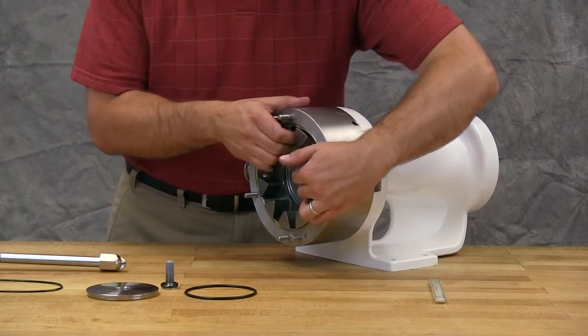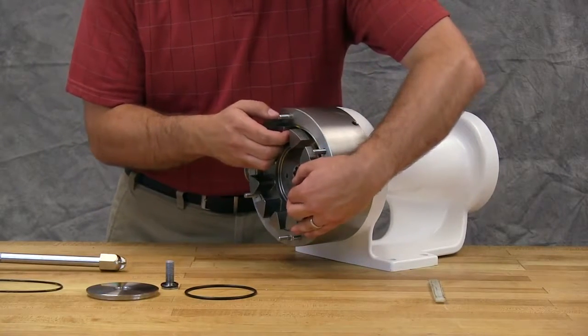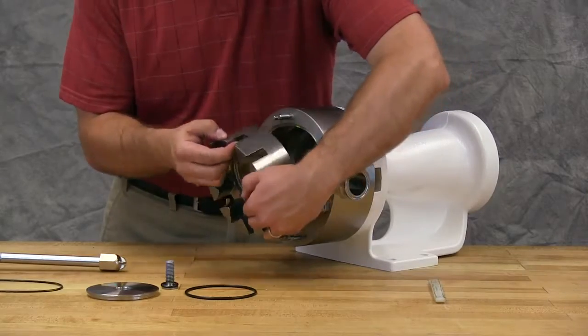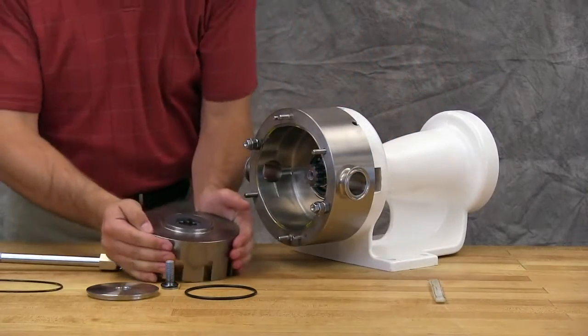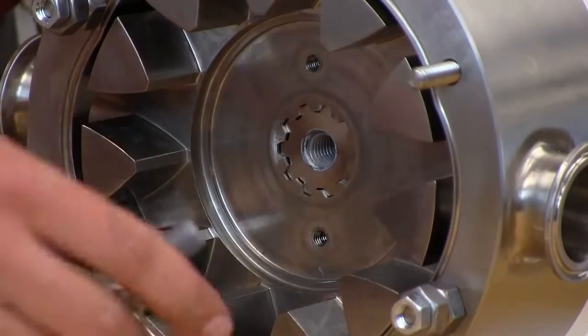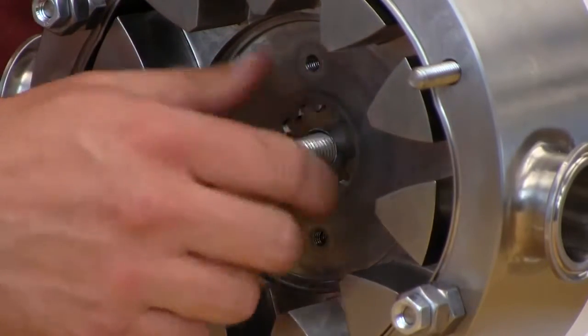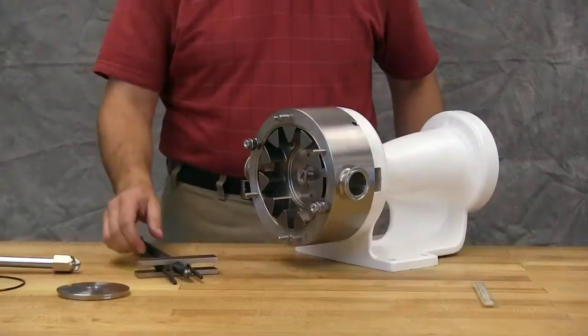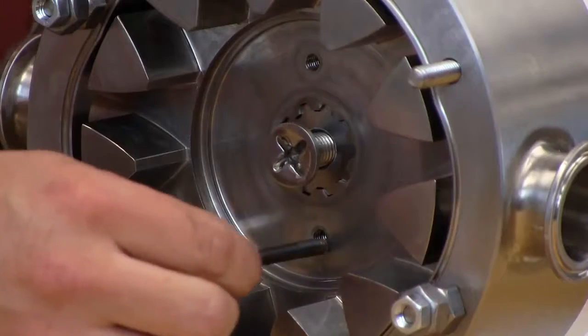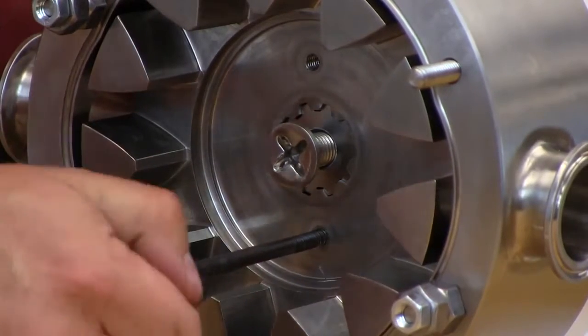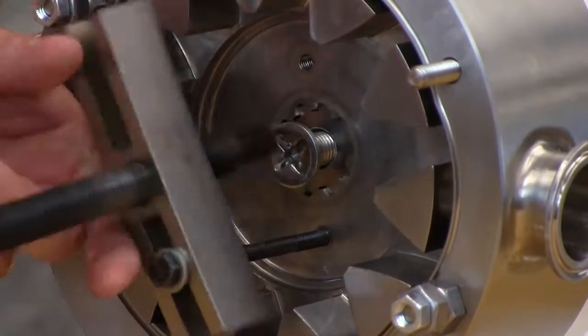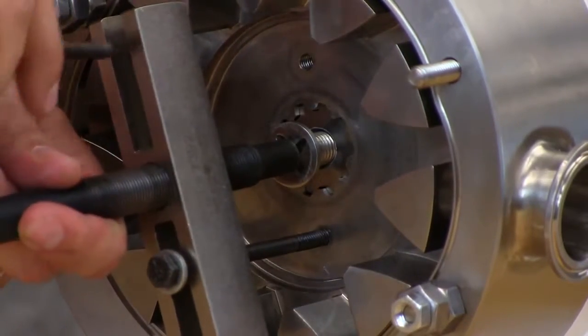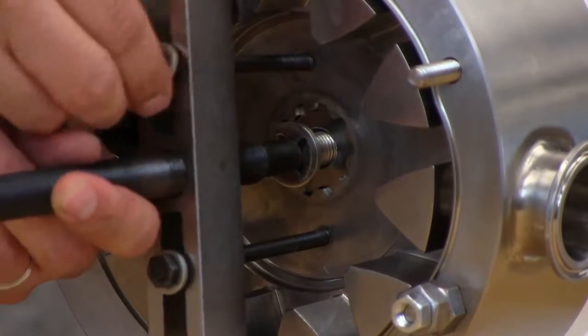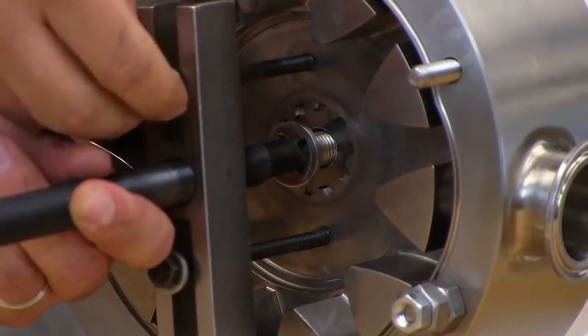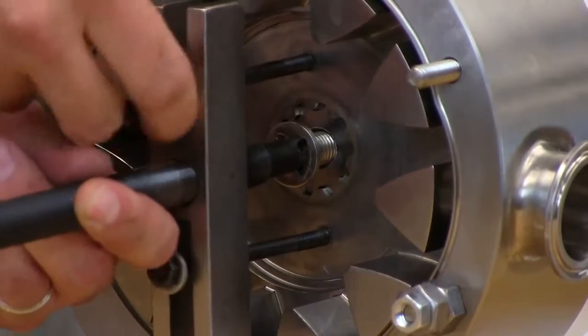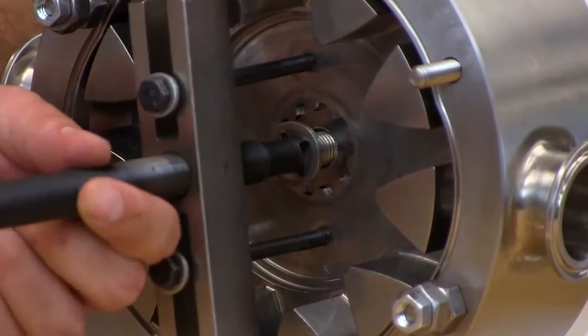Remove the rotor from the casing. The rotary member of the mechanical seal will be removed with the rotor. Take care not to damage the seal components when removing the rotor. If the rotor is not removable by hand, reinstall the rotor retainer and use a gear puller tool in the two drilled and tapped holes in the rotor face to assist in the removal of the rotor. The hole spacing and thread size for the gear puller holes is shown in the Technical Service Manual. These holes do not extend through the rotor and are not designed for jack screws.